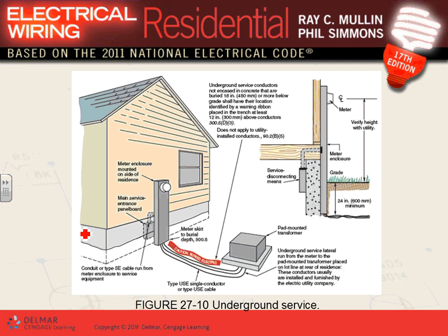So look at this installation, guys. Here's my transformer, pad-mounted transformer. Up to the meter, can you guys see the line side of the meter, this cable here? We're using USE cable. This is my service lateral. Can you guys see that, service lateral? From the meter into that building, can you guys see that?